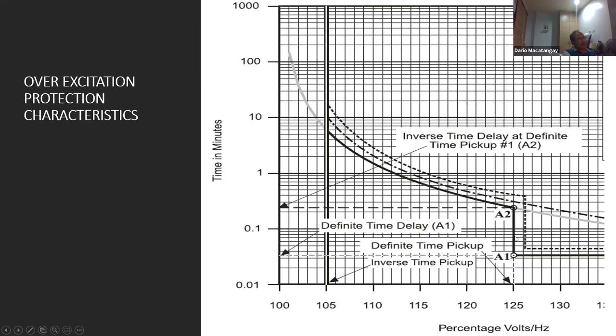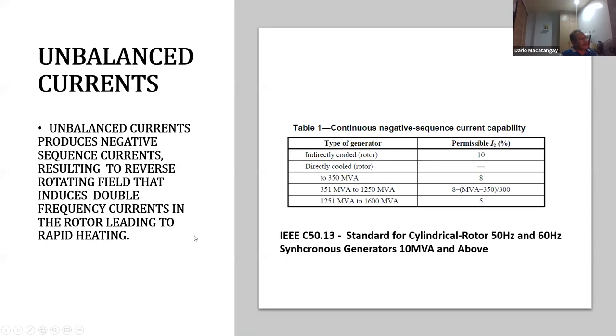Now, if it is an inverse time, this is an inverse time here, you can see that the tripping is dependent on the amount of volts per hertz and the time. So as the volts per hertz become smaller, the time to trip becomes bigger. So that's your protection characteristics for volts per hertz. Unbalanced currents. Unbalanced currents are caused by, let's say, a phase-to-phase fault or a series fault, one line open, or, for example, the imbalance is too high among the loads. Then you have unbalanced currents.